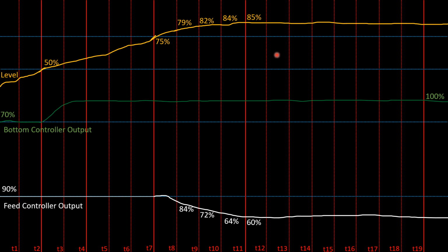Since this is not a PI controller, the level might not converge back to set point. It's more used to make sure the level does not get too high. However, there's also a chance it could converge to set point, but it's not guaranteed because this function does not have the integral component like a PI controller does, which will remove any offset.